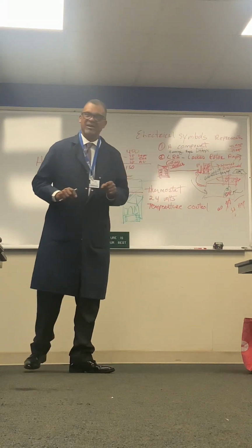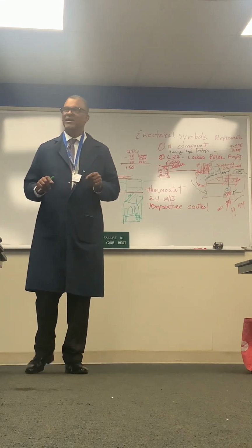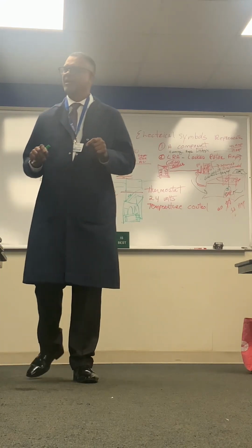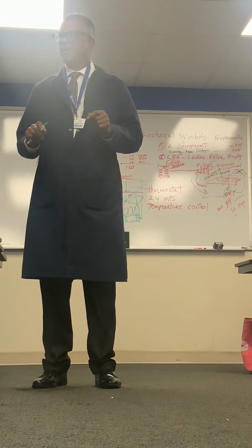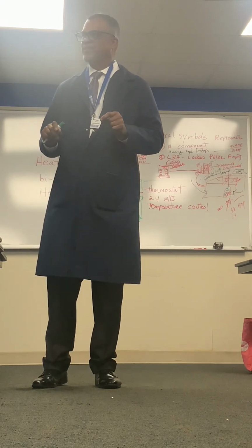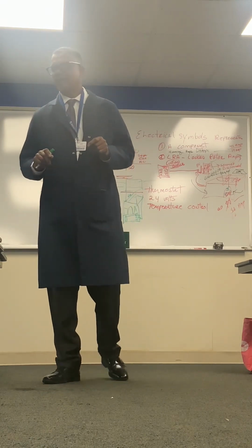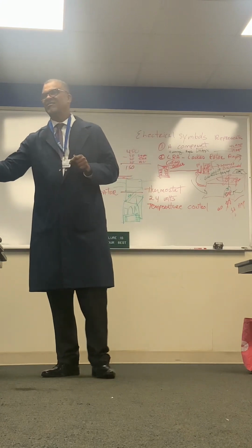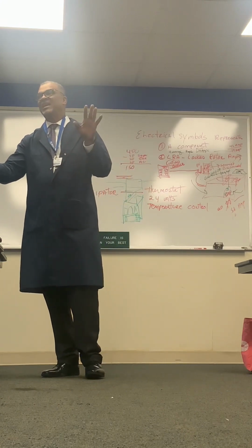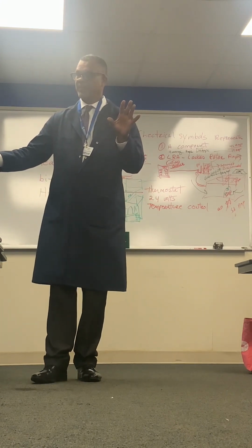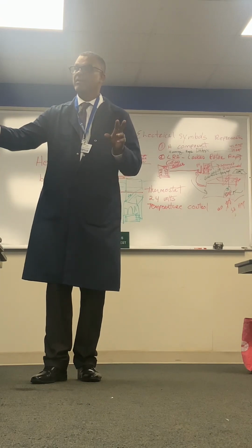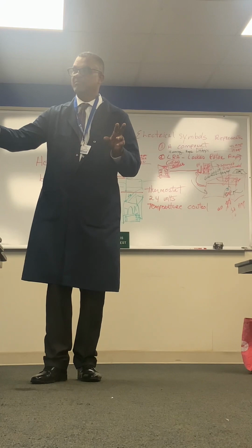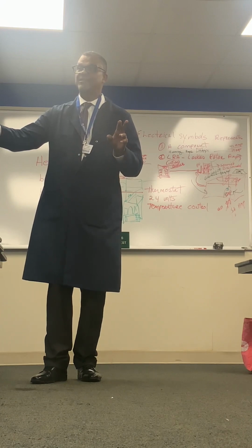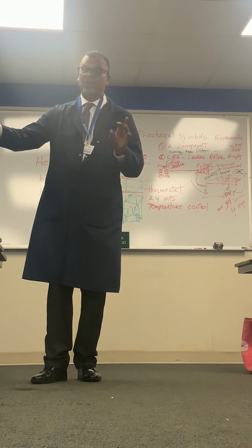I have a question. How is that box grounded with relation to the components on the inside? How is that box grounded? The component on the compressor gets grounded somewhere? The whole box, should it be grounded? This is not grounded. Only electrical items are grounded. I'm talking about the unit, the box where everything fits into. I don't see one. Case ground. It's called case, C-A-S-E, ground.